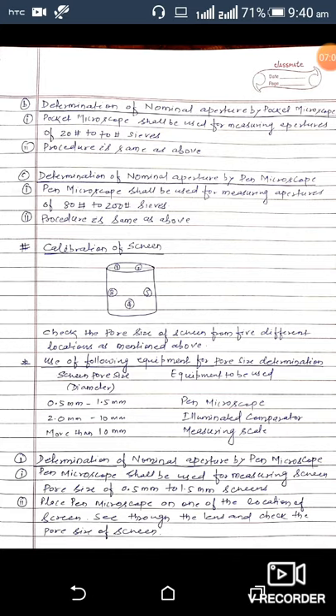The next topic is calibration of the screen. Check the pore size of a screen from five different locations as mentioned above. Use the following equipment for pore size determination: for screen pore size 0.5 mm to 1.5 mm, use a pen microscope; for 2 mm to 10 mm, use an illuminated comparator; and for more than 10 mm, a measuring scale shall be used.